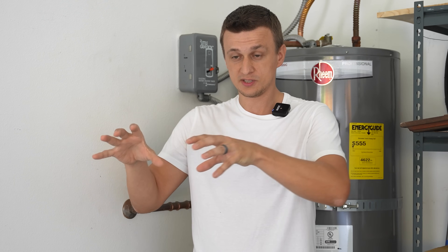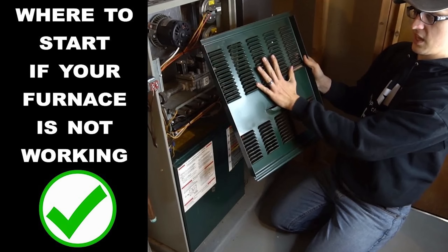The first, most easy, and most helpful thing you could do if your furnace is not working or intermittently not working: whenever your furnace fails to turn on, go down to the furnace, and on the bottom door there should be a little sight glass. Most furnaces will have this. Look through that sight glass and see if you see any blinking error codes. Write that down and then look up what that error code means. If you do have an error code, that will really help your troubleshooting, narrow it down, and make it a lot easier to track down what is causing that problem. If this furnace LED troubleshooting light sounds intimidating, I have a simpler video where I explain where to find that light and how to read what it means. I'll list that video in the description.